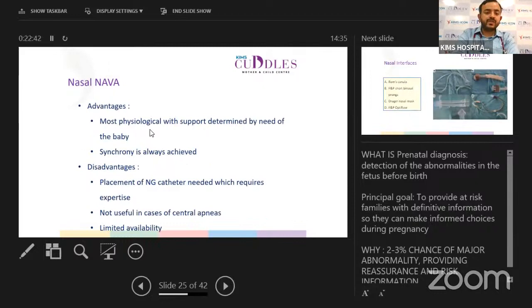The advantages are it is most physiological, with support determined by the need of the baby. Babies with increased respiratory distress tend to generate higher electrical activity of the diaphragm, and the higher electrical activity would mandate the ventilator to deliver higher support during inspiration. So in this way, babies who require higher support will get that additional support from the ventilator. And synchrony is always achieved, since the latency between detection and delivery is least in NAVA mode.